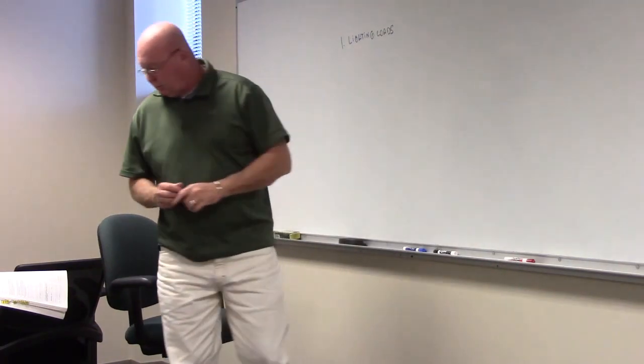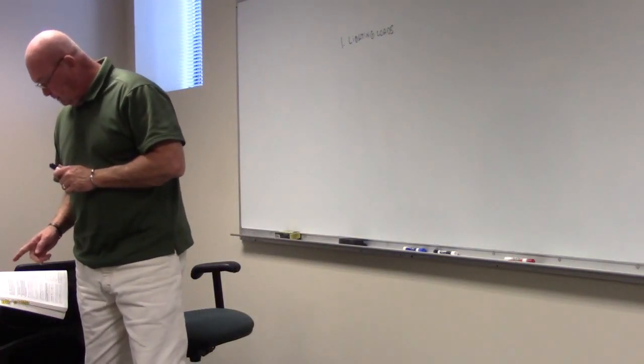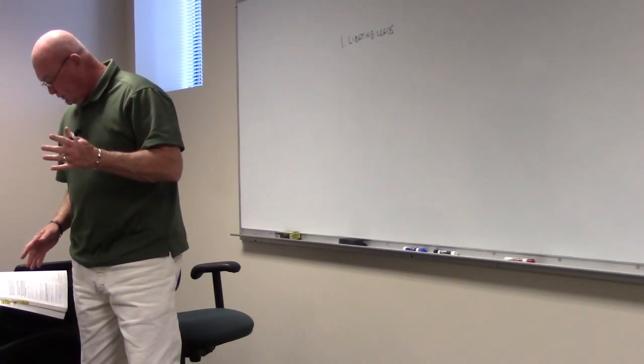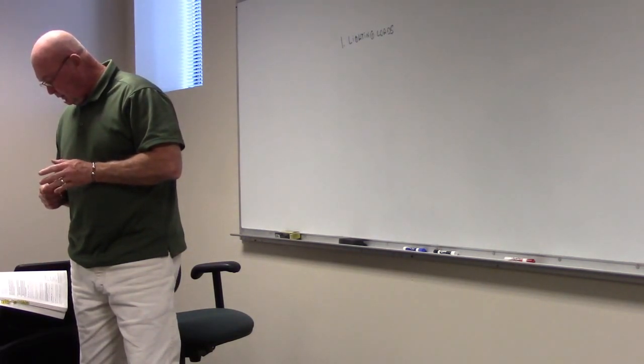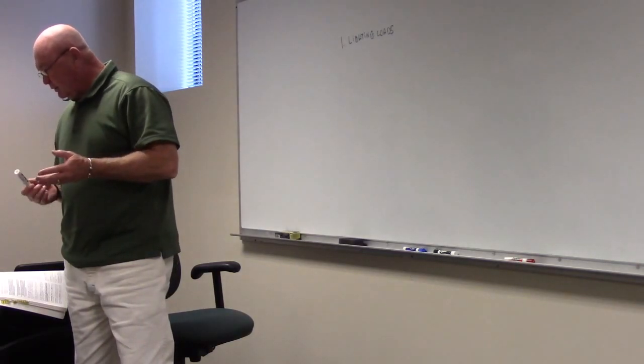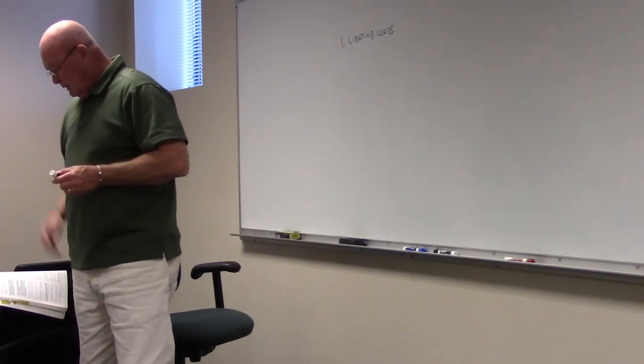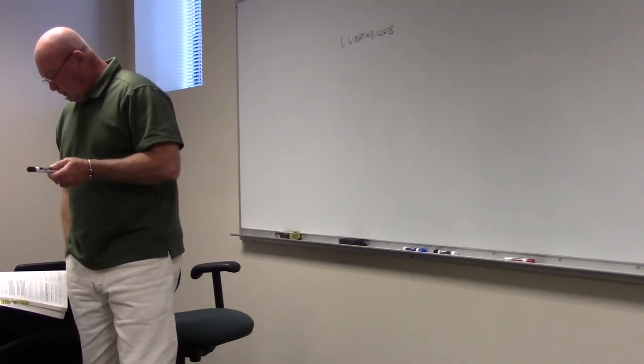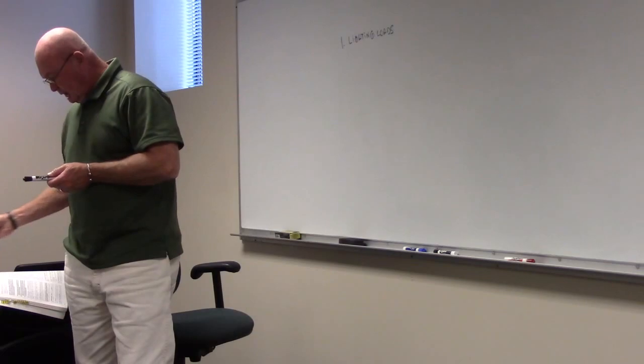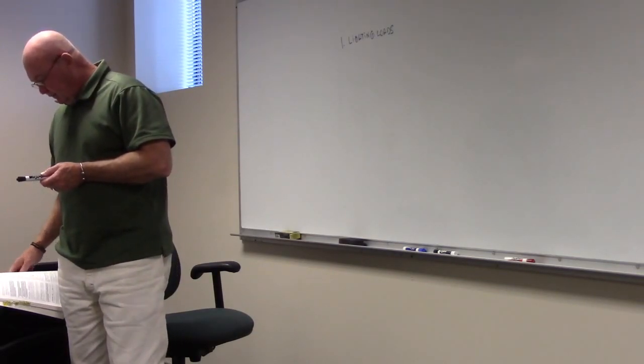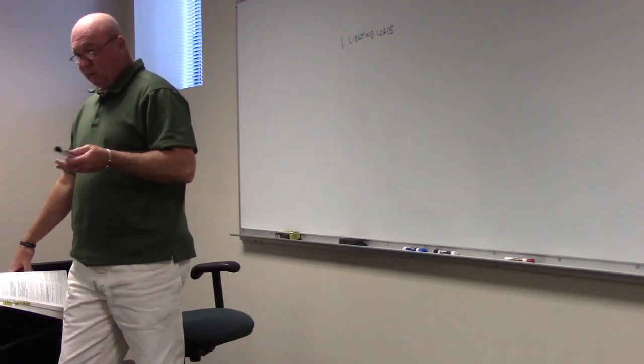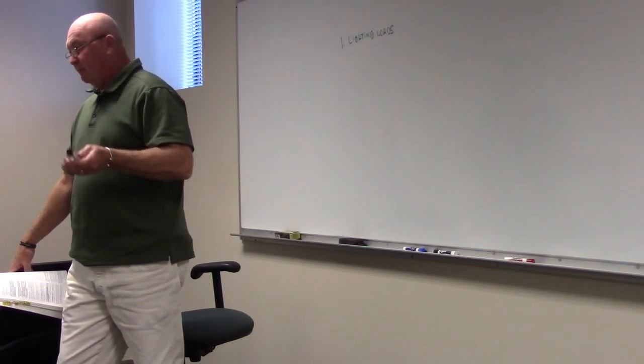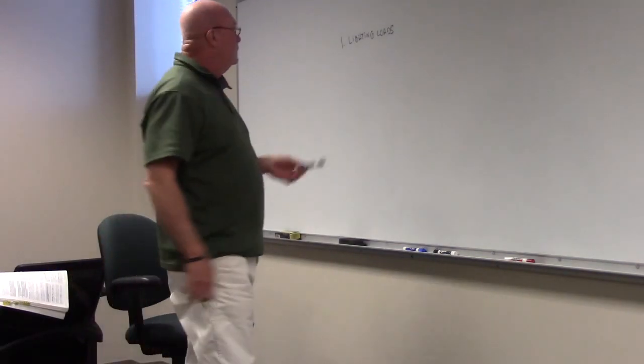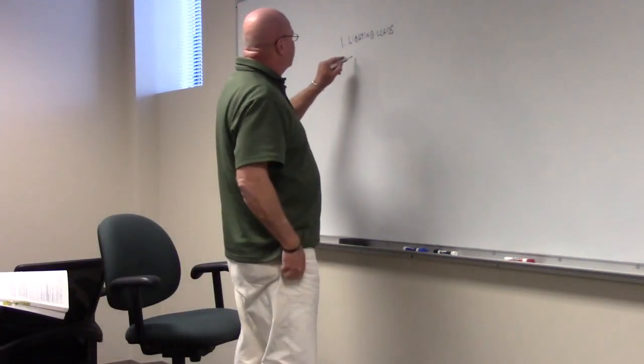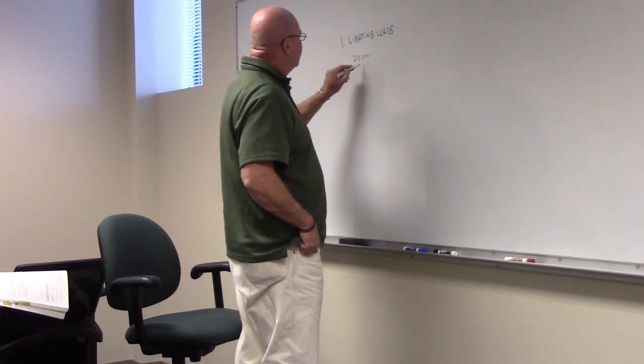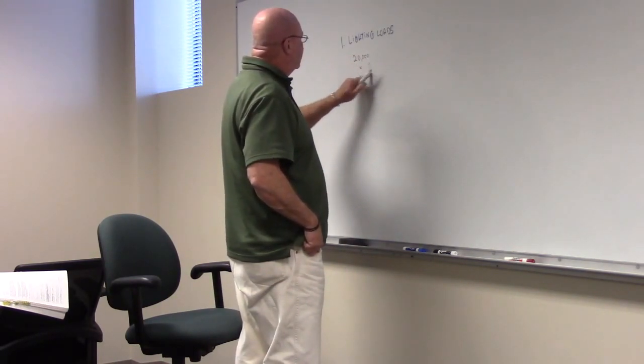Okay. Step number 2, multiply the floor area determined by step 1 by the unit load and count, which is kind of what we're just doing. Compare its value to the total installed lighting used for general illumination and use the larger of the two. So we're actually looking at whatever was installed, and you compare the two. Let's go back to this warehouse. Let's say we had 20,000 square foot times 3 times 0.25.